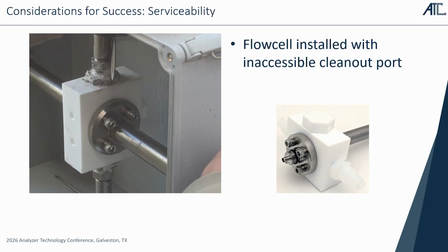Here's another example. Somebody actually put this flow cell into a box because they wanted it protected, since it's sitting outside. Well, there's supposed to be this cleanout port—that's what the hex head is here on the top right. The hex head's facing the back of the box. So you guys tell me, how are you going to take it out and clean it? Again, you got to wait for your shutdown, take it all apart, disassemble it, go back in. You can see they potted this in with some goop.